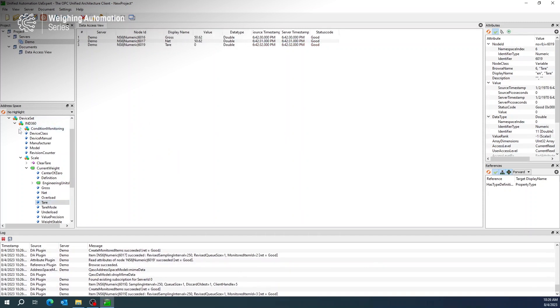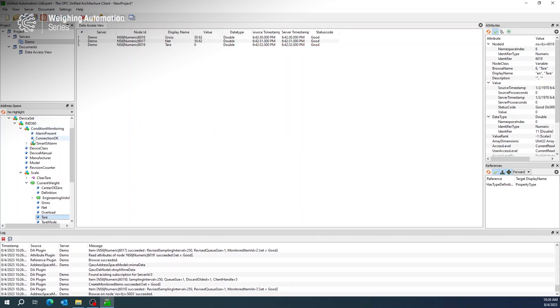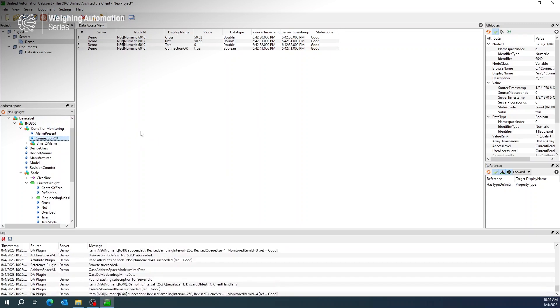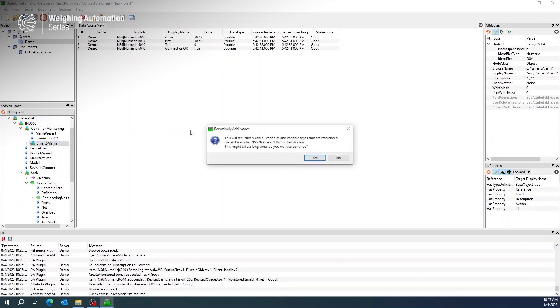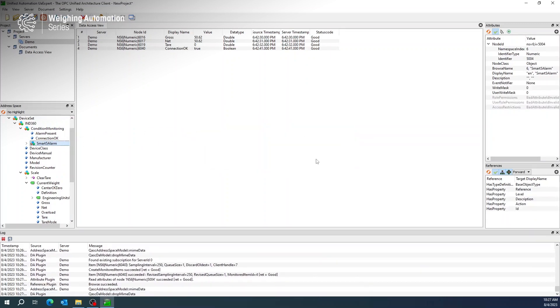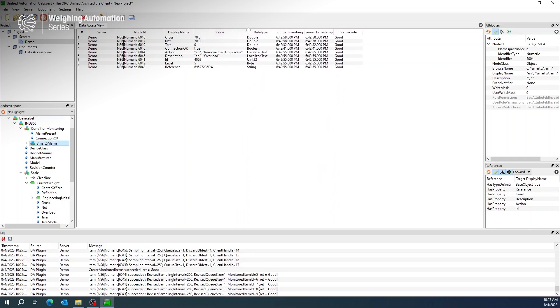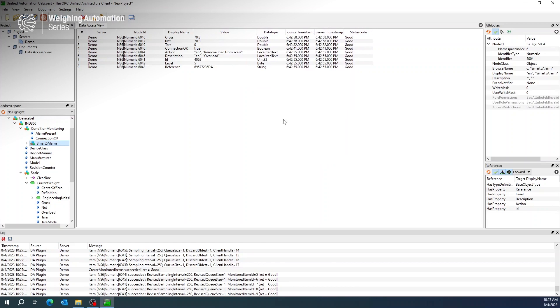Under Condition Monitoring, you will find status information such as Connection OK and SmartAlarm. We can see the weight value change on the screen. And as that goes above the rated capacity of the scale that we set, we see we get an overload alarm. That alarm will stay there until we remove weight from the scale, just as recommended on the screen.